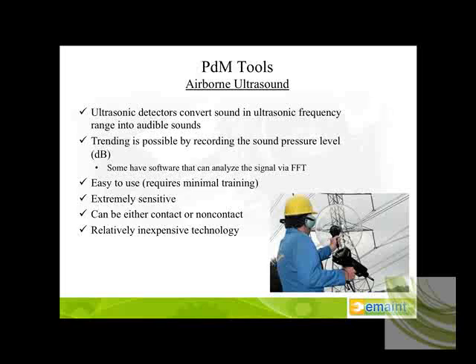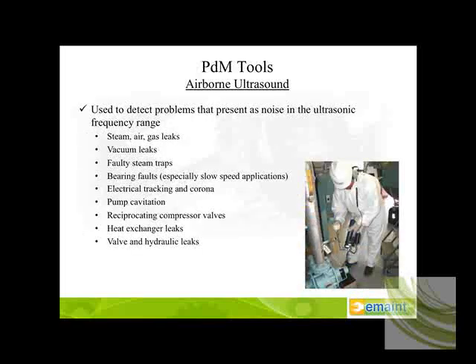The previous three, the full spectrum vibration analyzer, a thermal imaging camera with full temperature measurement capability, and oil labs can be fairly expensive to implement into an in-house type of program, whereas ultrasound can be fairly inexpensive. It can be utilized to detect problems in steam, air, gas leaks, vacuum leaks, faulty steam traps, bearing faults, especially low-speed applications. You'll find in talking to folks who perform vibration analysis on a regular basis that slow-speed applications can be difficult for a vibration analyst. Ultrasound can assist and lend itself to detection of bearing faults in low-speed applications.